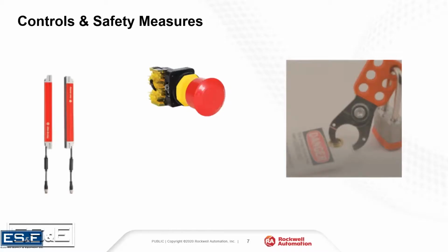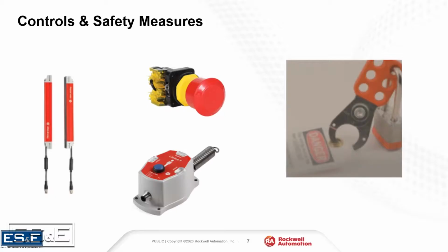And we also have to have emergency stop, but emergency stop is really not a safeguarding type of device or function. It's a separate function. Now, it might be wired together, no question. Many systems, emergency stop and safety devices and guarding interlocks, et cetera, are wired together. But in the standards and the engineering approaches today, it's really a different scenario. And same thing applies to a pull cord switch. These things are really just emergency stop devices. They're really not a safeguarding device. So think about that in, I guess, different contexts.